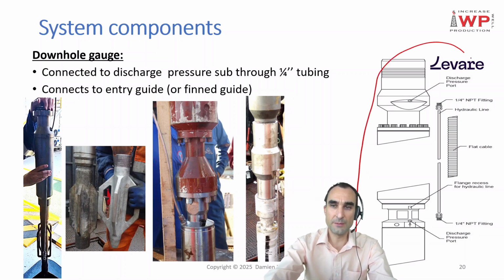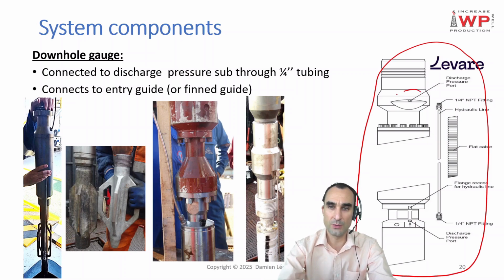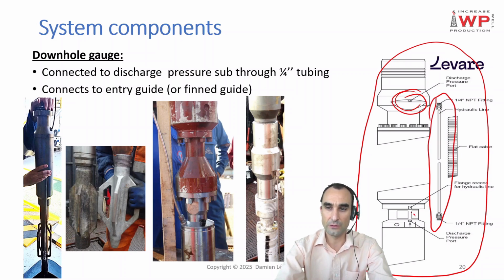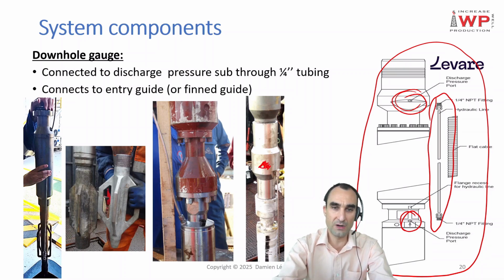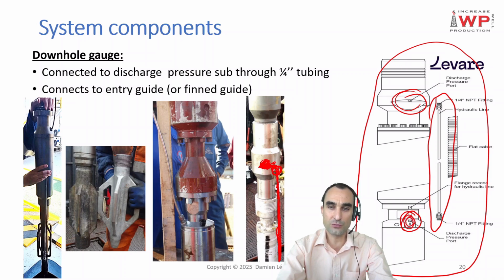So you actually have a schematic over there which shows that, where you have again the discharge pressure sub over there, this 1/4 of an inch tubing, and the discharge pressure port in your gauge. And so basically the pressure that you have inside the tubing there, you have a little hole on your discharge pressure sub so that it communicates with this 1/4 of an inch tubing. Then this 1/4 of an inch tubing, inside of it, you have the same pressure as what you have at the discharge of your pump. And so it sends back this pressure to this discharge pressure port at the gauge level, and so it will allow the gauge to read this pressure.